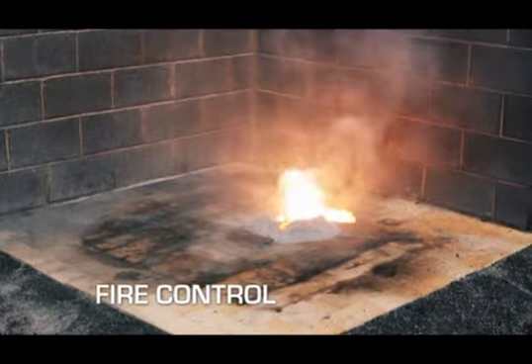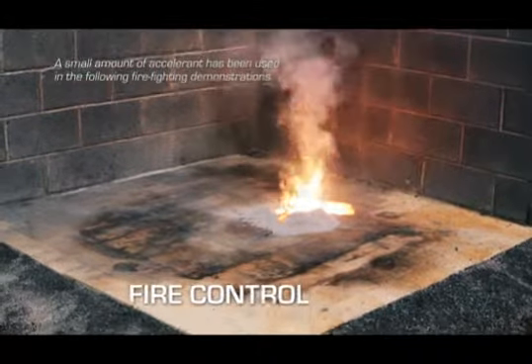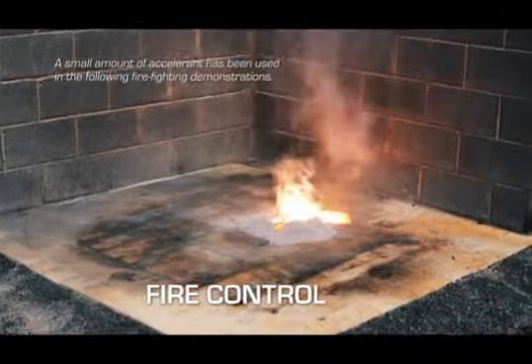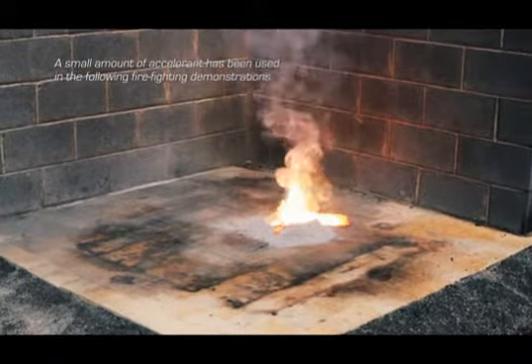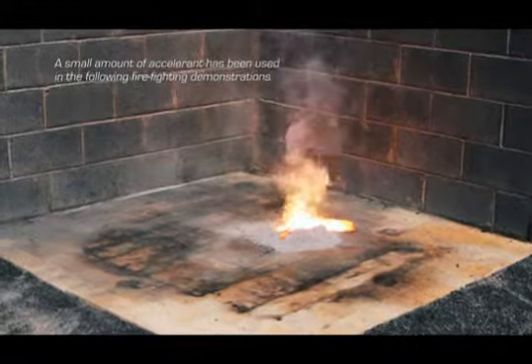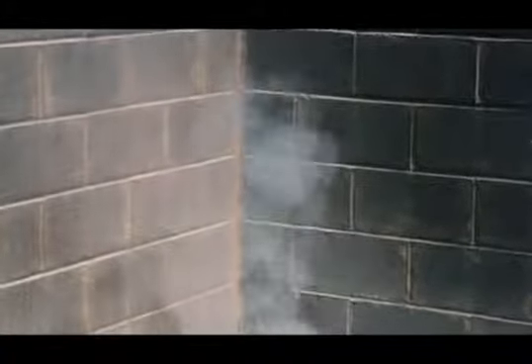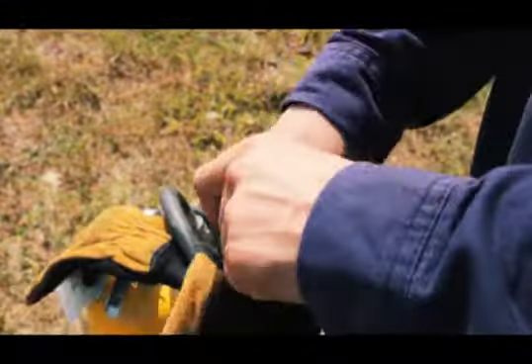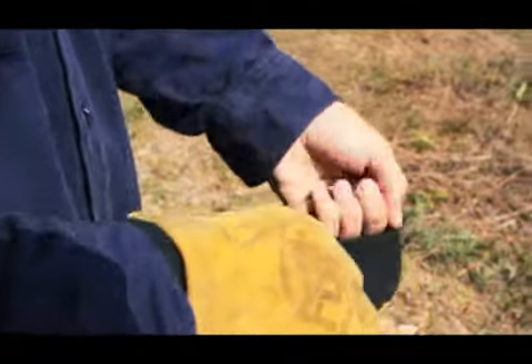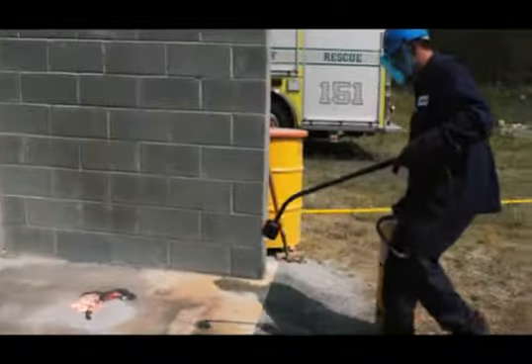Since it is almost impossible to extinguish an active dry aluminum powder fire, solutions to the problem are focused on the control of these fires in the incipient stage. Aluminum powder fires are characterized by the emission of extremely bright light, very high heat, and the generation of large amounts of white smoke. Suppressing a metal powder fire should only be attempted by personnel who are trained in the special precautions required for fighting fires involving such combustible metals.